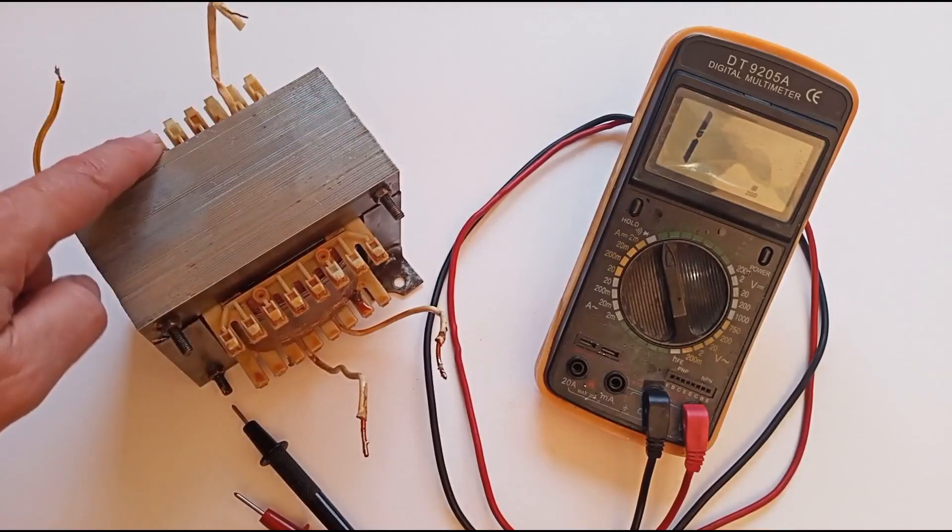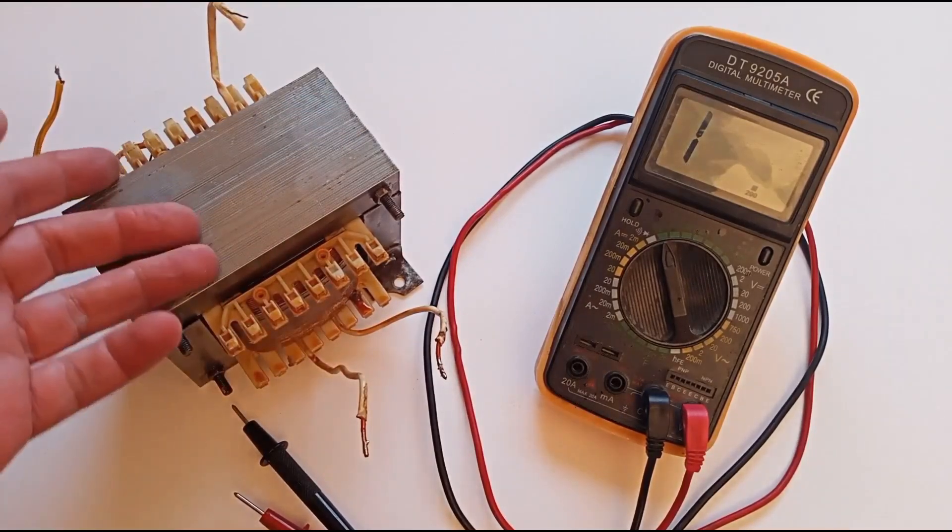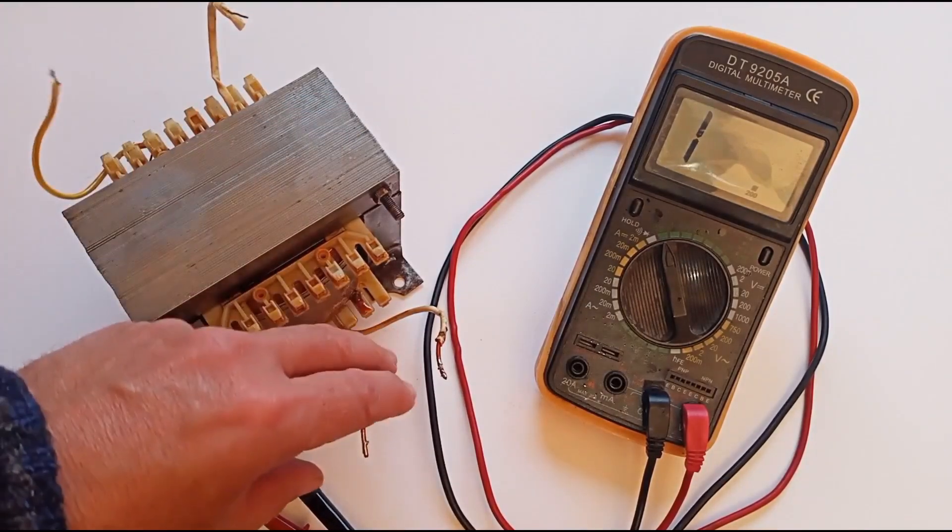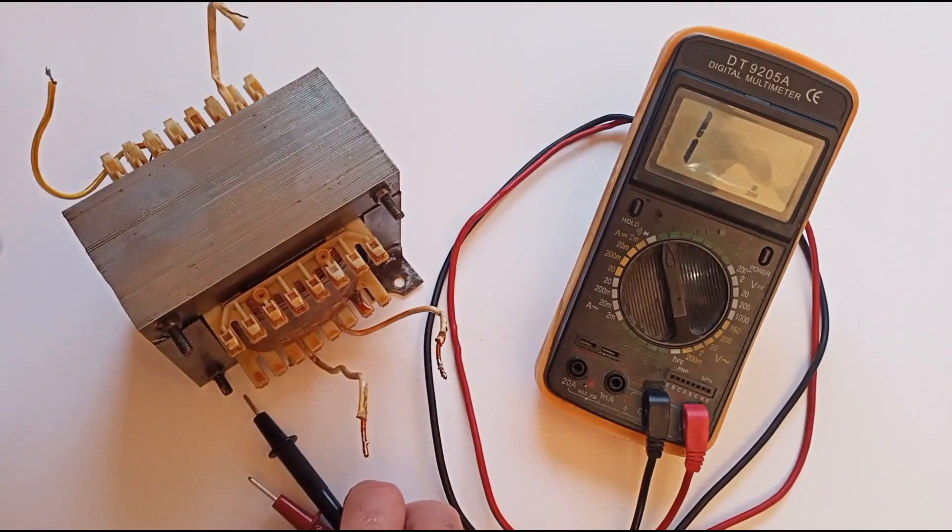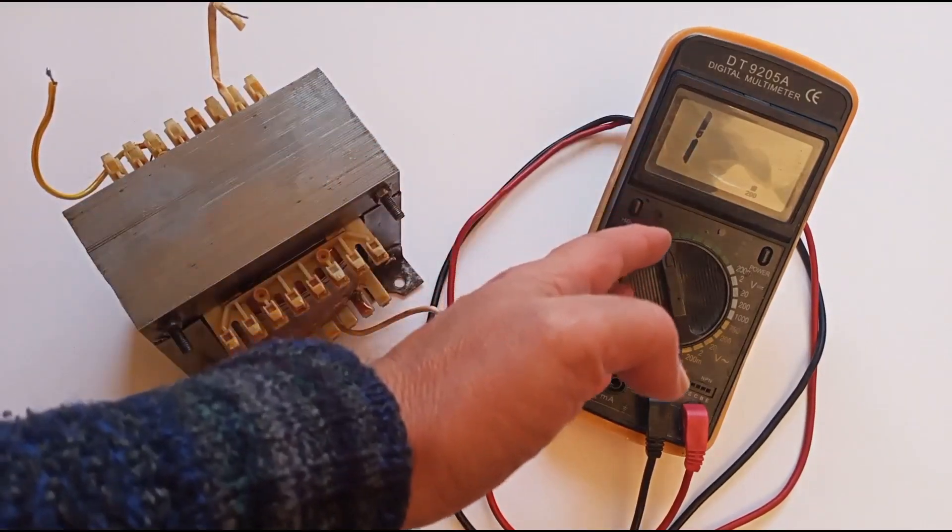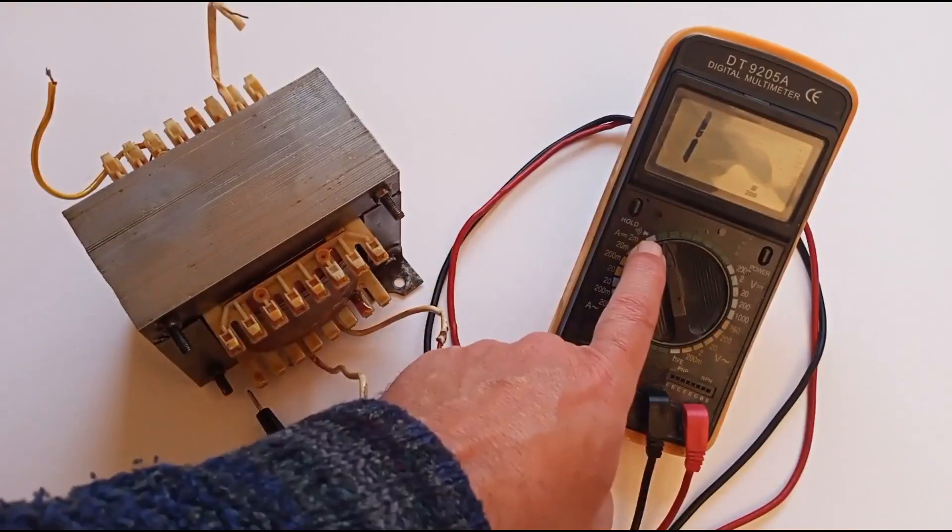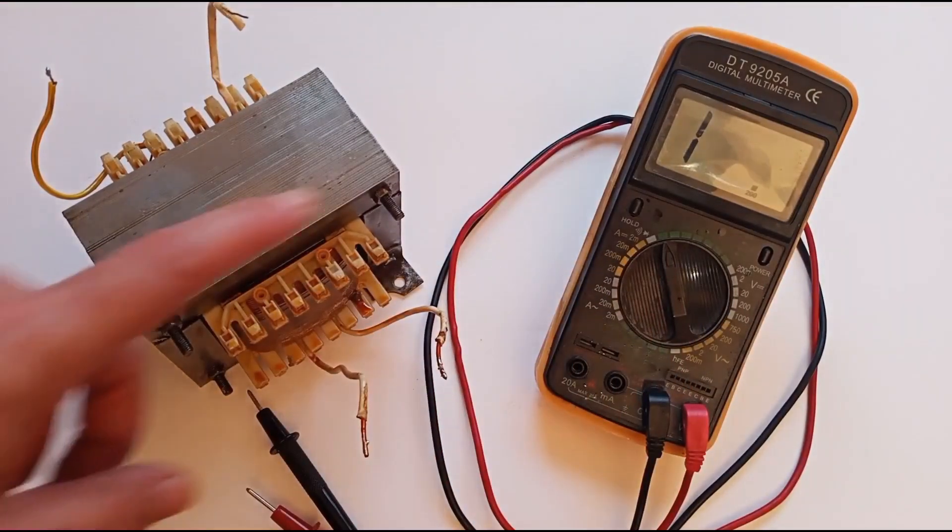Measuring the electrical resistance of a transformer's windings is a useful technique to identify the primary and secondary windings and distinguish high voltage windings from low voltage ones. A multimeter set to the resistance measurement scale (ohms) is required.